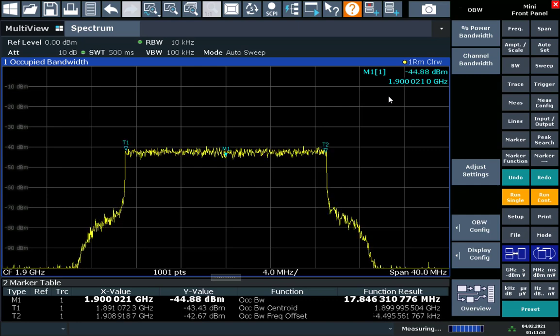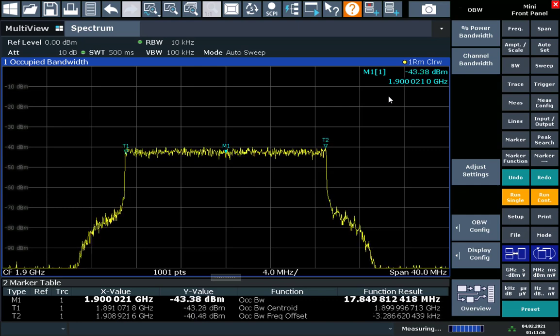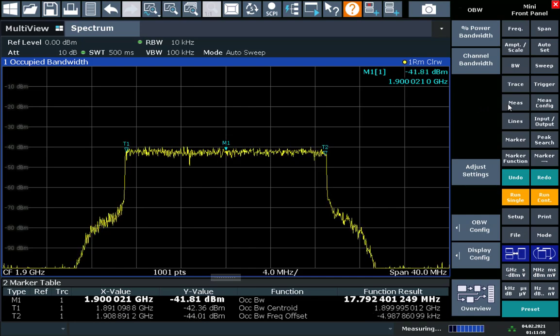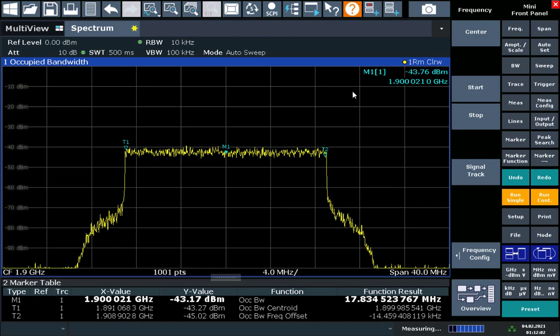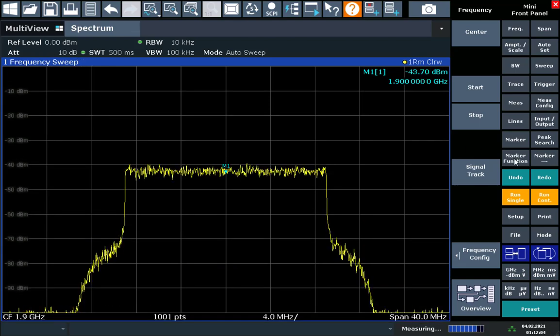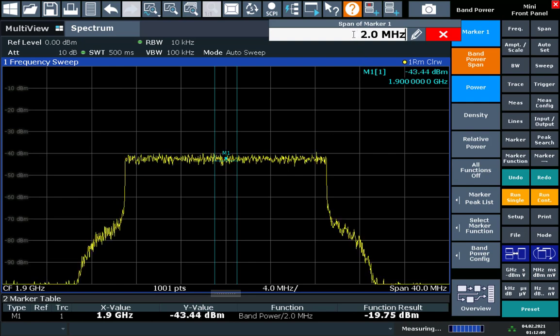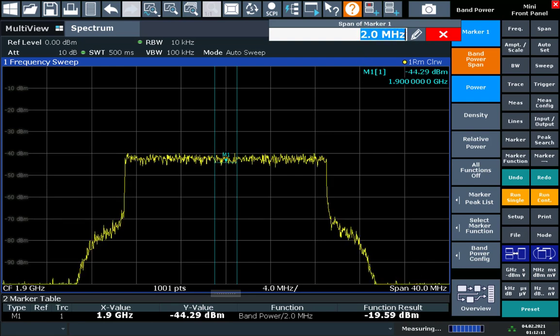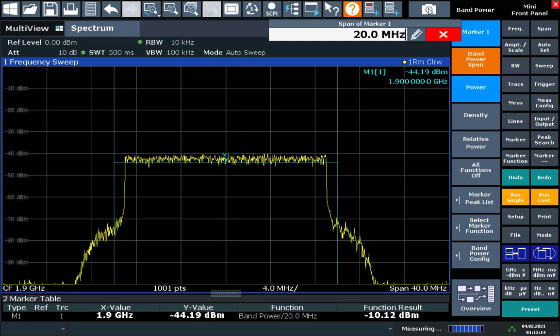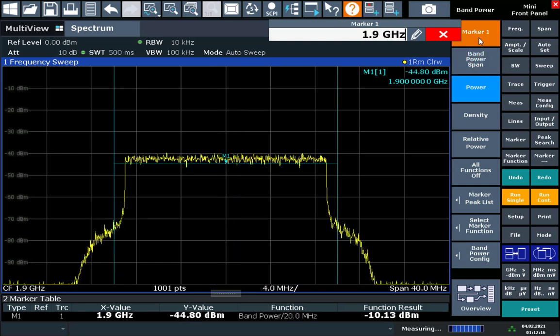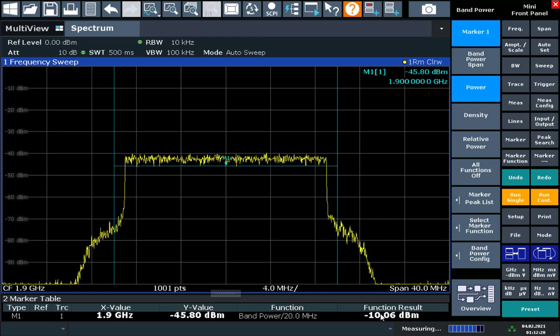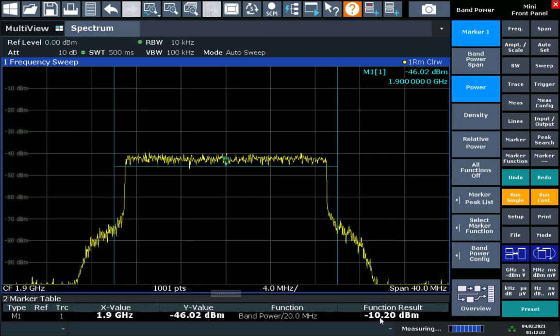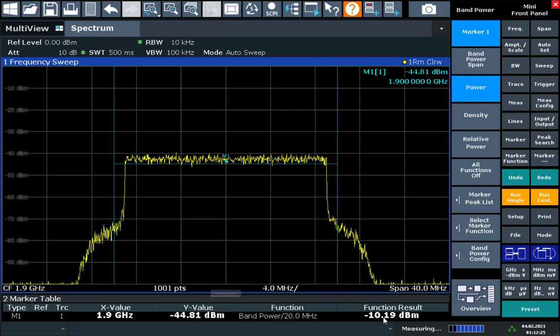So let's measure the total channel power. Starting out we'll use a band power marker function. For that we're going to change this measurement mode from occupied bandwidth back to a regular frequency sweep. We're going to add a marker function, band power, and we'll change the span of that to 20 MHz. We can set the frequency of that marker to 1900 MHz. And here we see in the functional result about minus 10 dBm, what we expect from the signal generator, plus any cable losses.